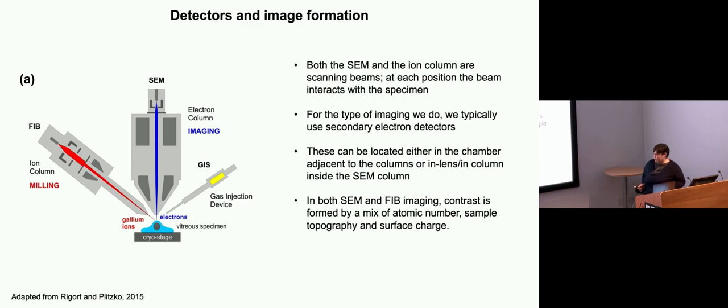So we tend to use secondary electron detectors. And we can also use these in-lens in-column detectors as well. For both of these, the images, what you see in terms of contrast is formed as a mix of the topography of the surface and the atomic number, and also charging plays a role.